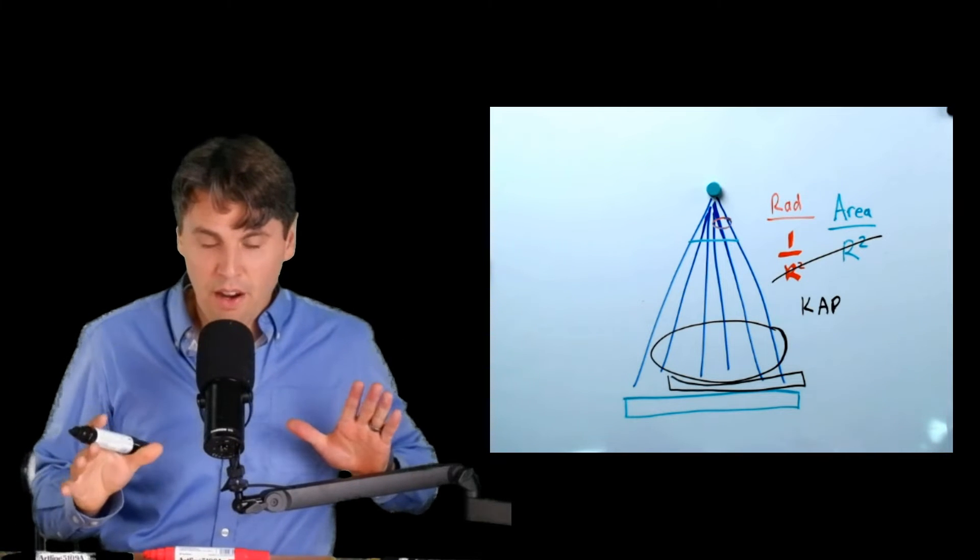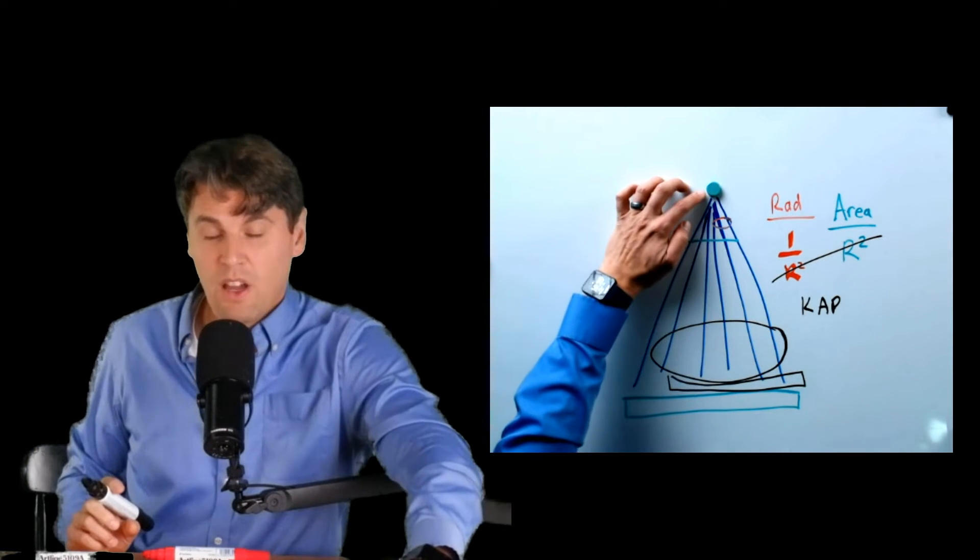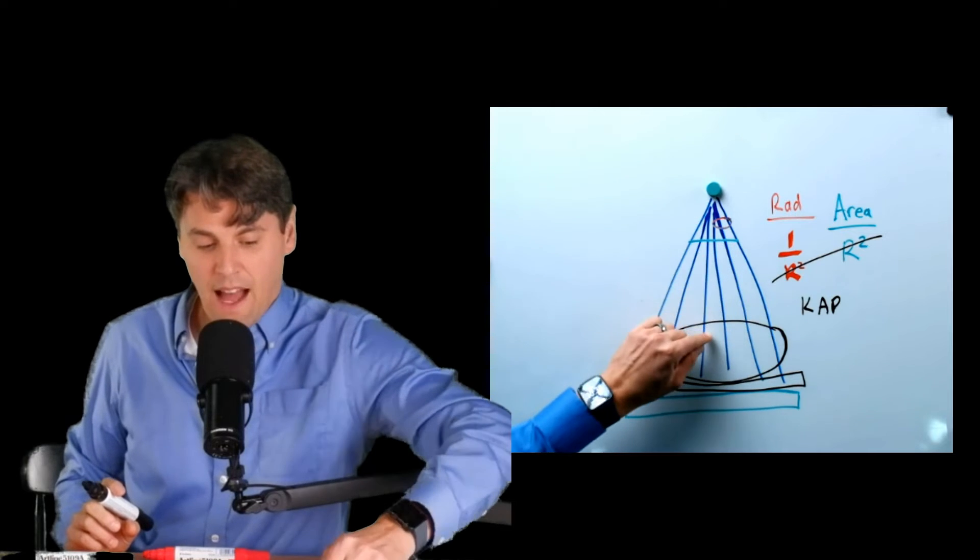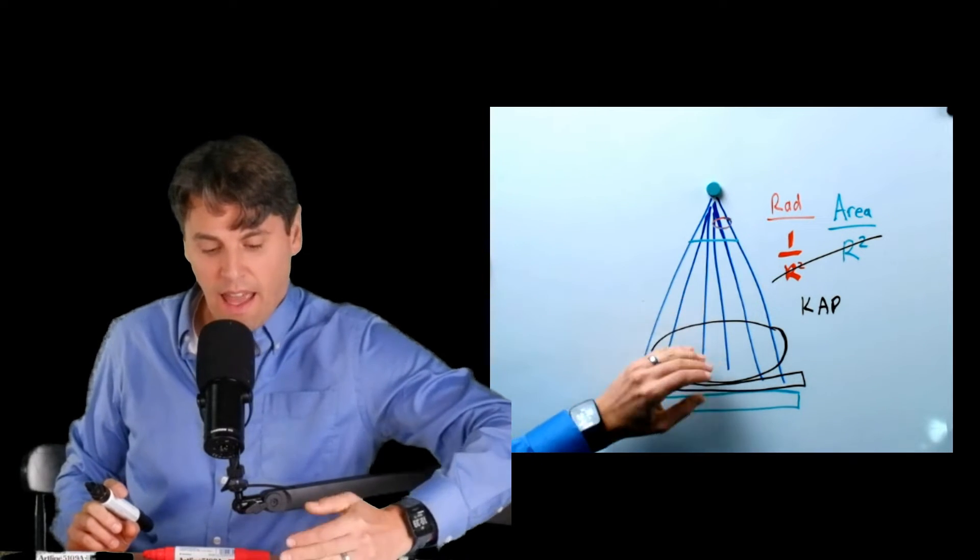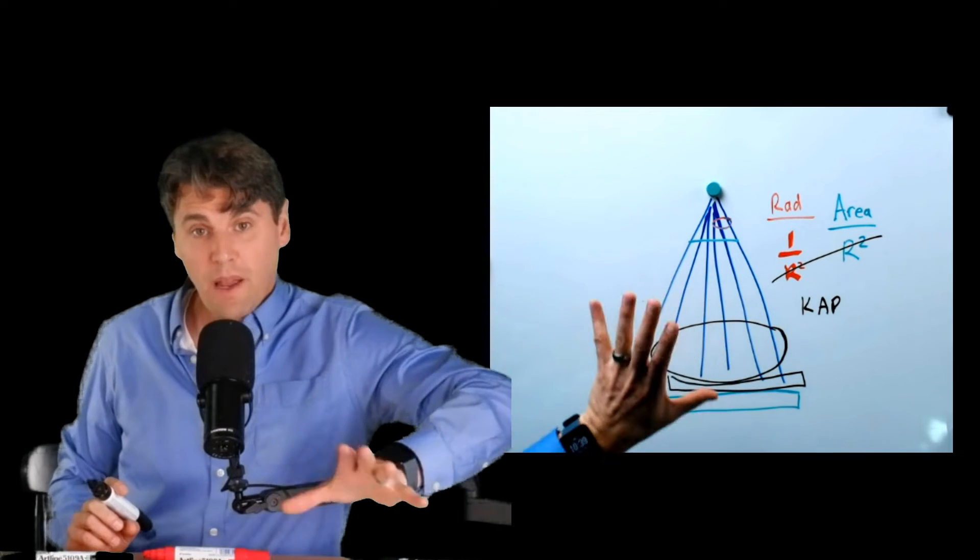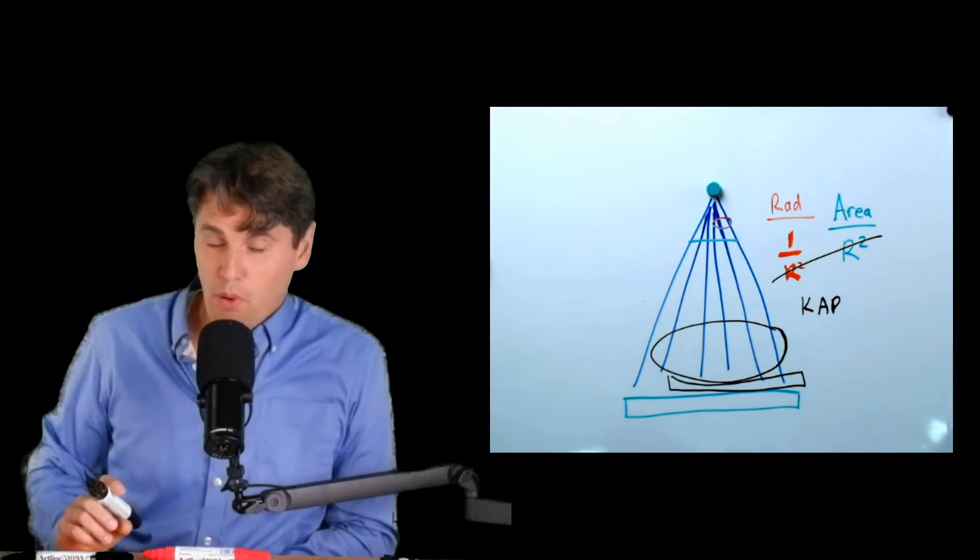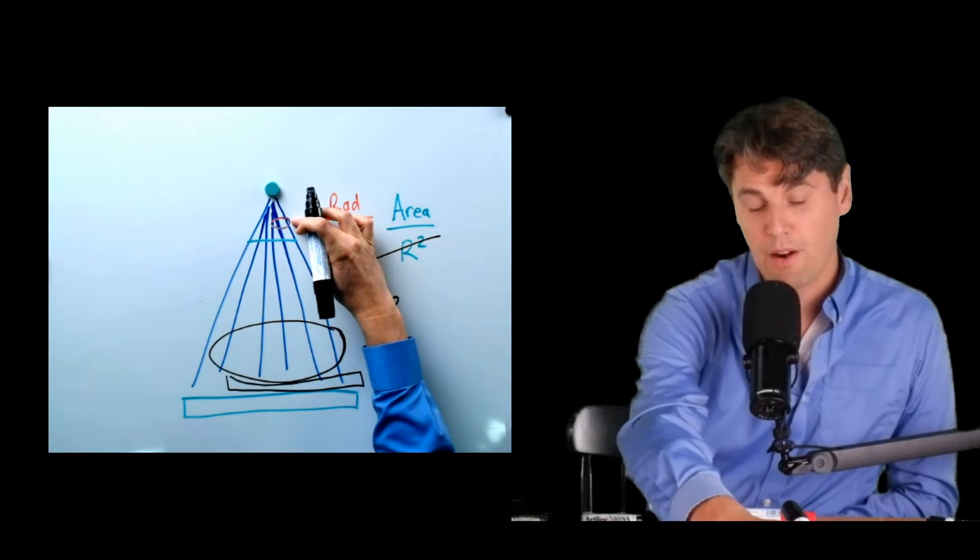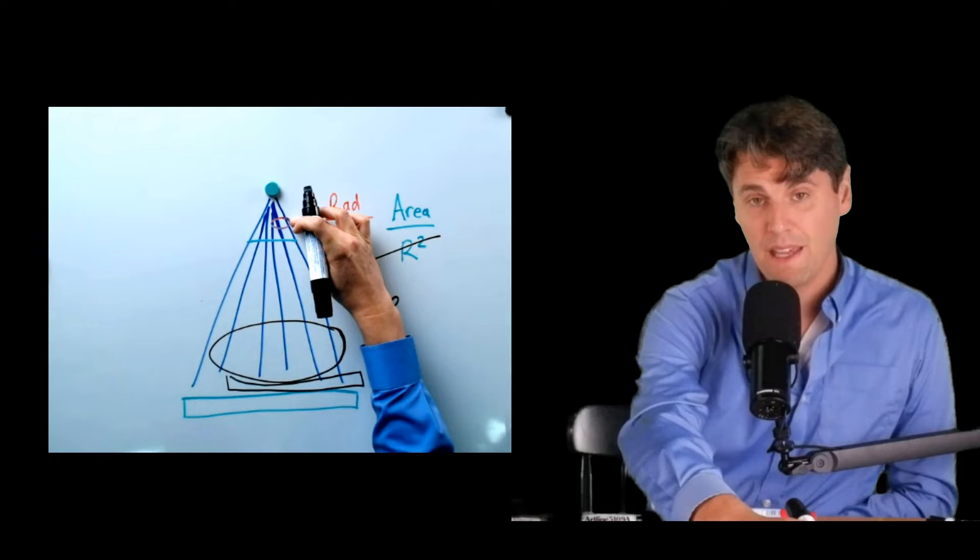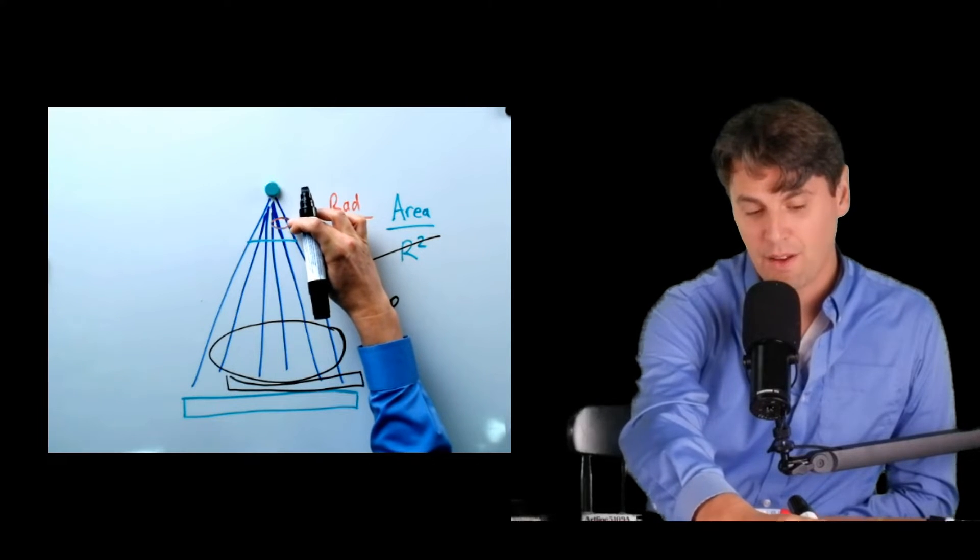Namely, the Kerma area product or the dose area product do not depend on the distance from the x-ray tube. So this is a nice thing. As you move your patient up or down, the Kerma area product that you're going to be reporting is actually going to be the same. And that's why you can make your Kerma area product measurements up here, right close to the x-ray tube.